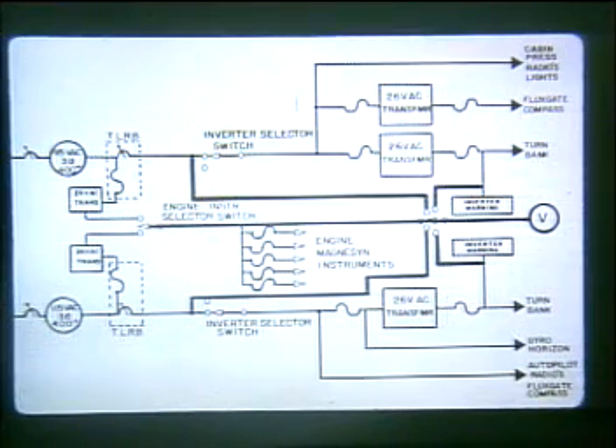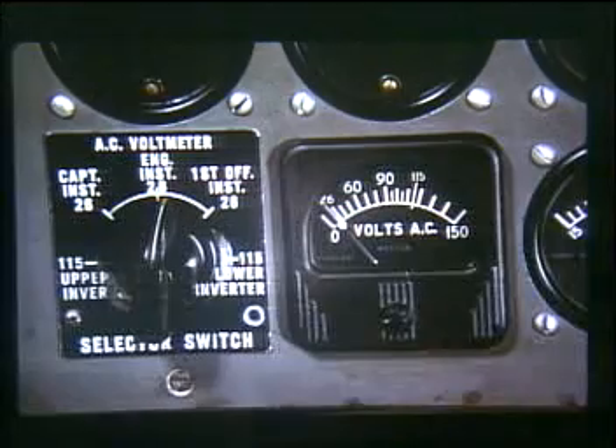An AC voltmeter and an associated selector switch on the lower left side of the generator panel permits monitoring of the voltage output of both inverters. The 26-volt AC available to both the captain's and first officer's flight instruments, and the 26-volt AC available to the engine instruments. The selector switch is normally left in the vertical or 26-volt AC engine instrument position to monitor this voltage. The inverter warning lights will illuminate if flight instrument voltage should fail.